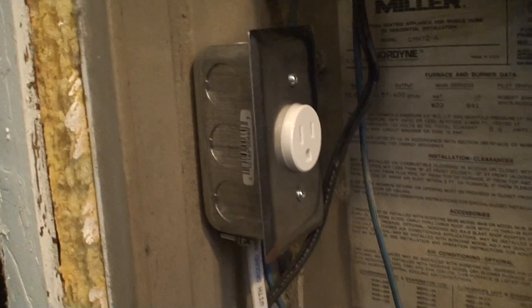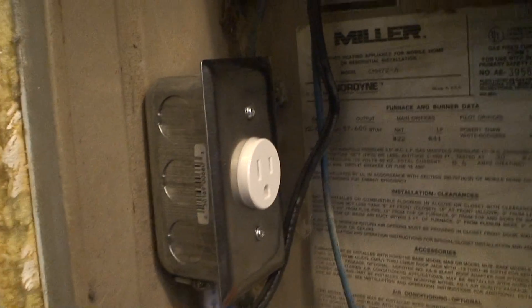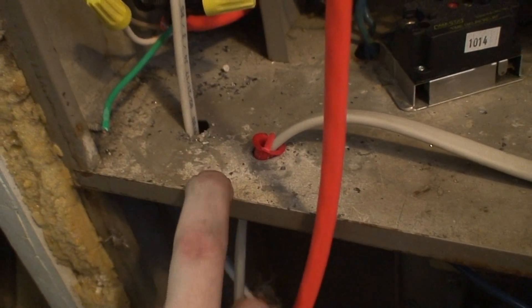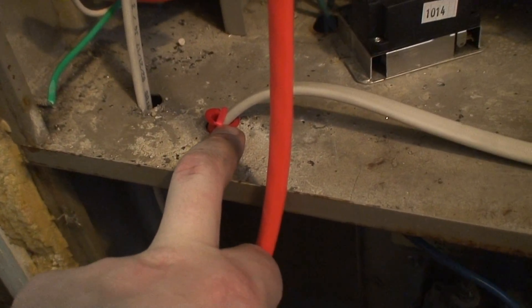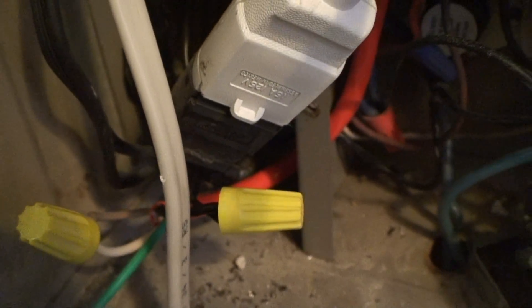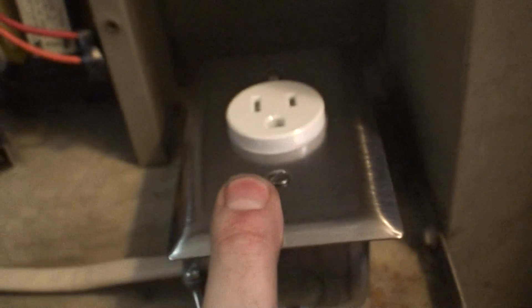Okay, back at the furnace — wiring is complete. We're going to drill a couple holes through the plate. This is somewhat tough metal to drill through. Anti-short bushing — I'll put another one here. This is the outlet for the generator; the extension cord comes in and connects into there. This outlet here is the mains power coming in from the panel.